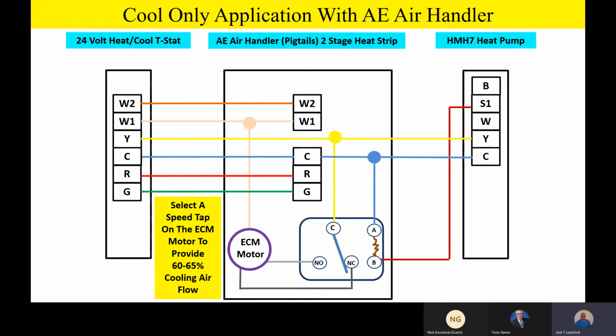Now, let me caution you. If you do that, there's 2 things I want to stress. Be sure and put a bi-flow filter dryer on the liquid line because it's still a heat pump. It thinks it's a heat pump in the outdoor unit. It may go into an exercise mode on the reversing valve to keep it fluid and to keep it moving and all that stuff. And so for 30 seconds or 15 seconds, you could have reverse flow on the refrigerant. So make sure you put a bi-flow filter dryer, even though it's on a straight cool application.